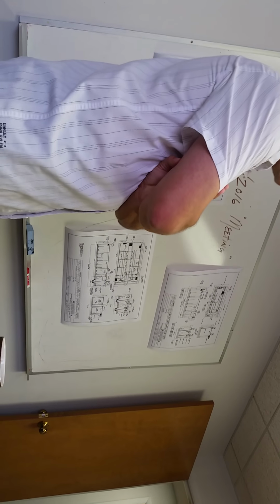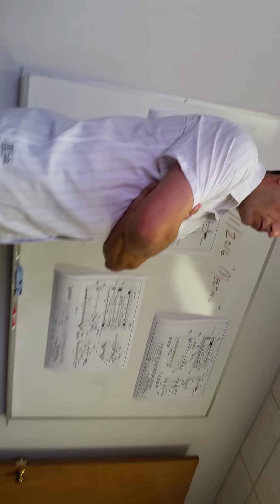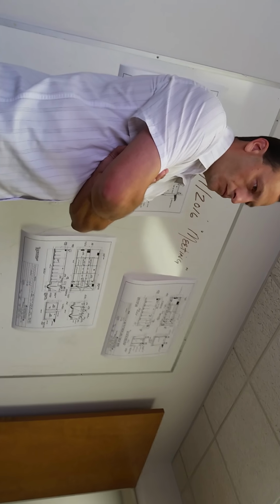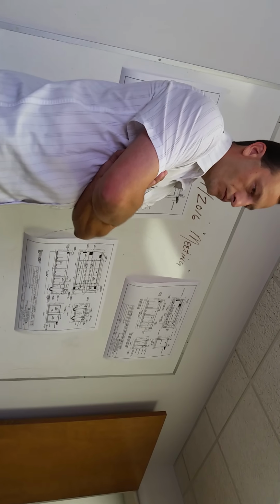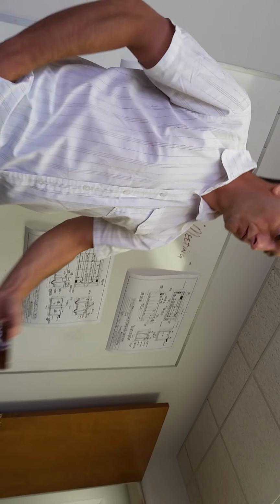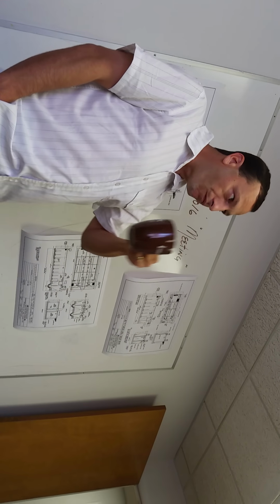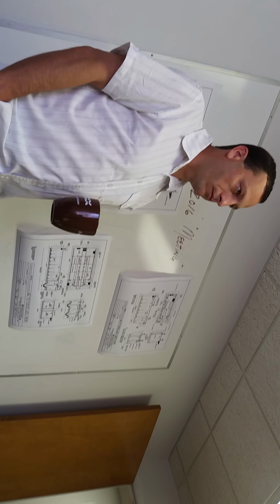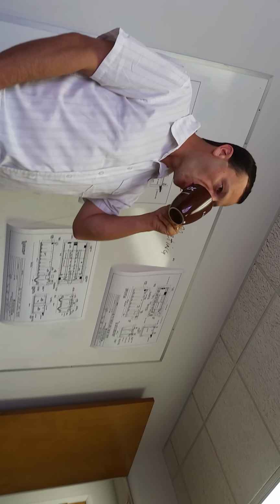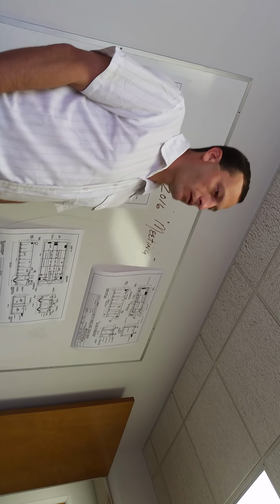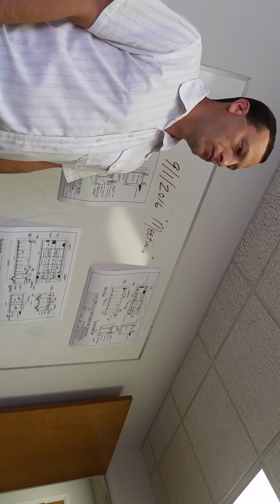What we have found lately, though, is that with low-flow toilets, low-flow shower heads, and laundry using far less water, we're getting higher BOD levels in fewer gallons per day. So we do have to take that into account when designing our systems. In New York, for example, we have to design at 320 BOD instead of 240.